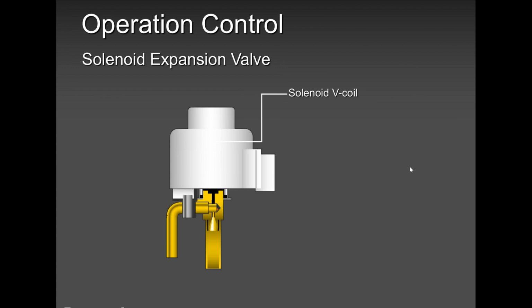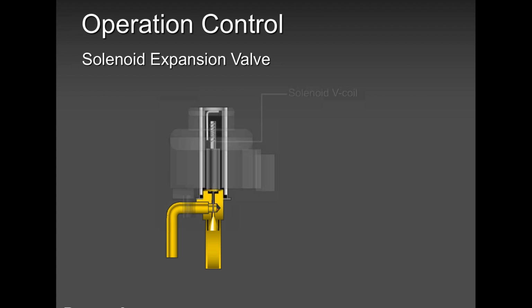So this electronic expansion valve is so sensitive, made out of copper, plastic, a little bit of metal, a little bit of aluminum. So you've got to be very gentle with this, especially when you're replacing it. Why? Because this rotor here that goes up and down depending on the load is made of a super hard plastic. Now, can you imagine replacing this and brazing somewhere here without applying any cold damp cloth? That plastic is going to melt. You're going to finish your job. You're going to waste a lot of hours, even though you're doing your due diligence. And the next thing, you have the same problem.